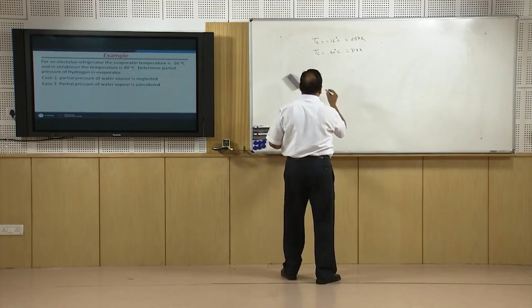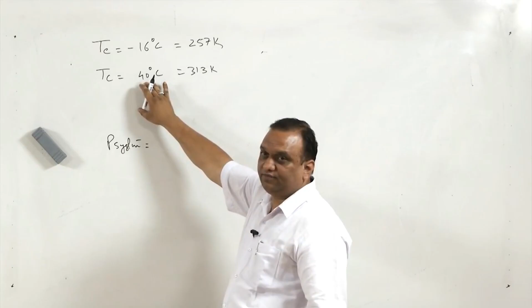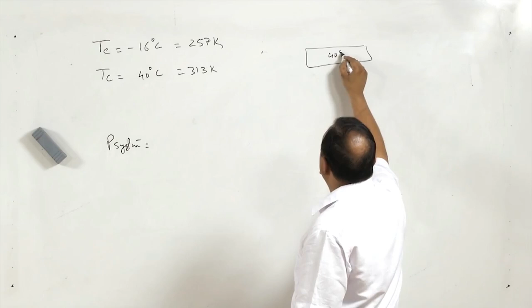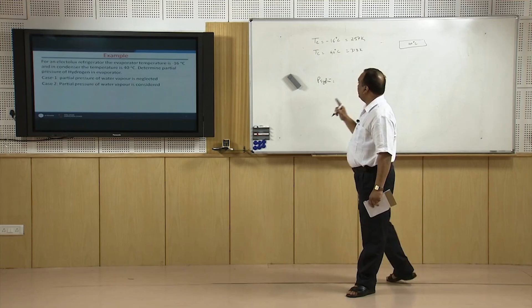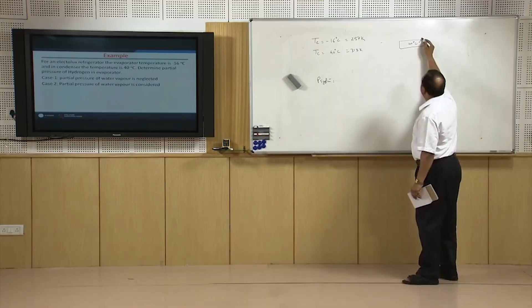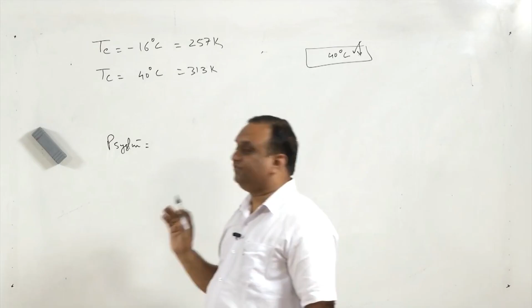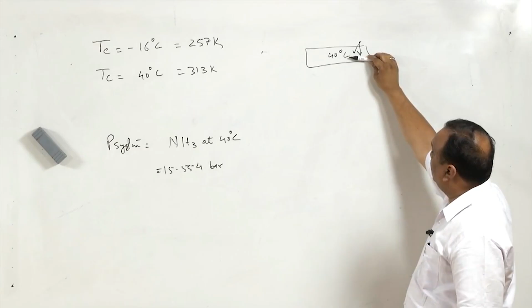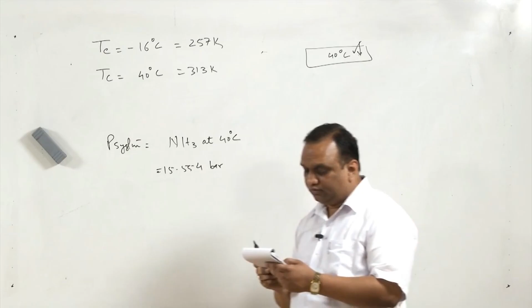The system pressure is equal to the pressure of ammonia at 40 degrees centigrade. Why? The total system pressure is the pressure of ammonia at 40 degrees centigrade, because in the condenser, where temperature is 40 degrees centigrade, there is only anhydrous ammonia. It means there is pure ammonia inside the condenser, and when it is getting condensed, the saturation pressure at 40 degrees centigrade is the total pressure of the system, and that is 15.554 bar. So, ammonia is condensing in the condenser at 15.554 bar.